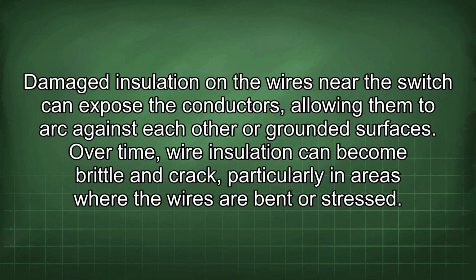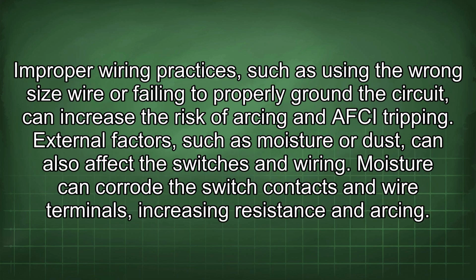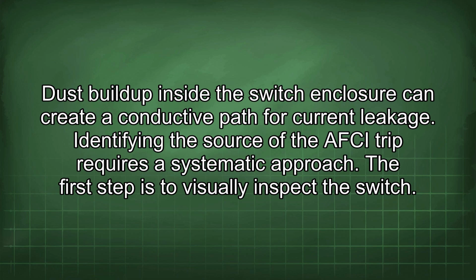Damaged insulation on the wires near the switch can expose the conductors, allowing them to arc against each other or grounded surfaces. Over time, wire insulation can become brittle and crack, particularly in areas where the wires are bent or stressed. Improper wiring practices, such as using the wrong size wire or failing to properly ground the circuit, can increase the risk of arcing and AFCI tripping. External factors, such as moisture or dust, can also affect the switches and wiring. Moisture can corrode the switch contacts and wire terminals, increasing resistance and arcing. Dust buildup inside the switch enclosure can create a conductive path for current leakage.